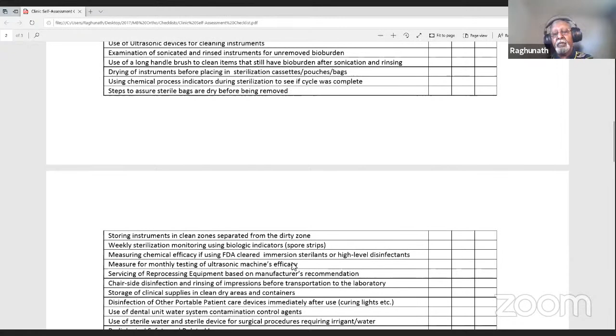Then measuring chemical efficacy if FDA cleared immersion sterilants are used. So you have to use the dipstick or the dip strip to check, if you're using any glutaraldehydes, how efficacious it is, at least once a week. Measure for monthly testing of ultrasonic machines efficacy. Servicing of reprocessing equipment based on manufacturer's recommendation.